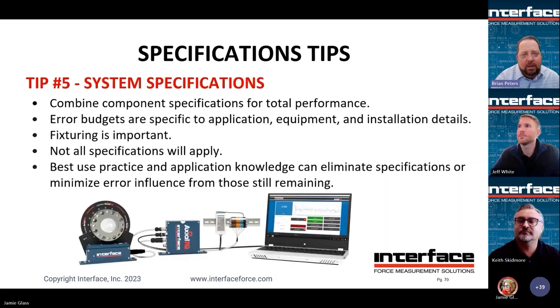Last one. So, system specification. This is kind of the culmination. We zoomed in on the sensor. Really understand the fact that there are specifications for the entire system. So you're going to have your instrumentation. You're going to have potentially cable influence. You're also going to have maybe some influence from fixturing. So again, how we attach to a load cell, how we calibrate, how we can then hit those performance specifications, it's going to be a function of how we're attaching to that load cell.